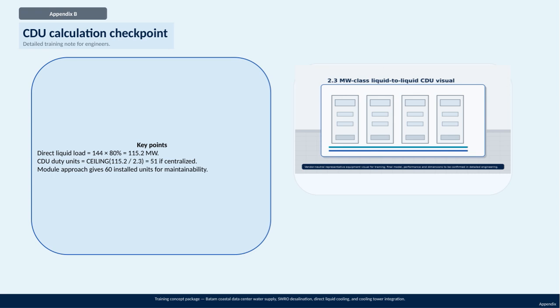Based on this load, if we use a centralized CDU system, the number of duty units required is calculated by dividing 115.2 by 2.3 megawatts per unit and rounding up, resulting in 51 units. However, to improve maintainability, we've adopted a module approach, which means installing 60 units instead.